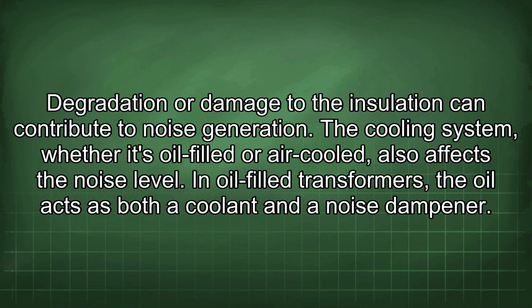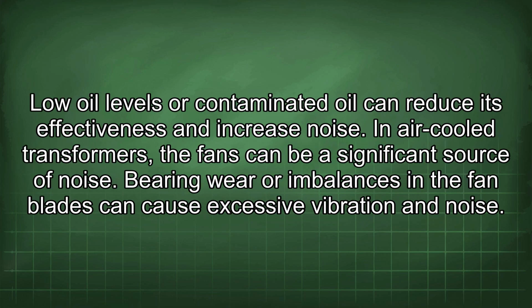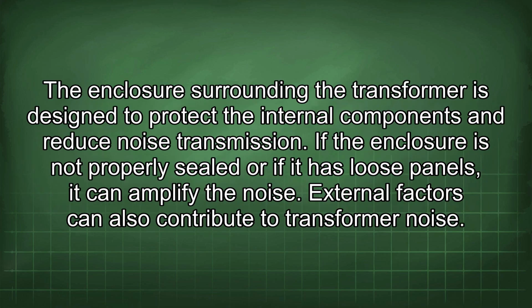The cooling system, whether it's oil-filled or air-cooled, also affects the noise level. In oil-filled transformers, the oil acts as both a coolant and a noise dampener. Low oil levels or contaminated oil can reduce its effectiveness and increase noise. In air-cooled transformers, the fans can be a significant source of noise. Wear or imbalances in the fan blades can cause excessive vibration and noise. The enclosure surrounding the transformer is designed to protect the internal components and reduce noise transmission. If the enclosure is not properly sealed or has loose panels, it can amplify the noise.